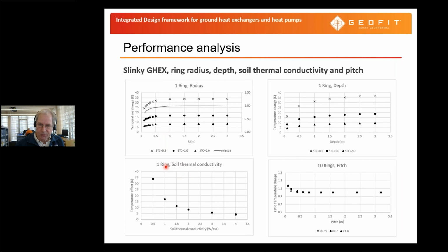We can also look at the soil thermal conductivity, and here we can see that at very low soil conductivity, like 0.5 in a completely dry sand, we have a big temperature effect of the soil thermal conductivity, but once it is above 1.5, this effect again decreases. So here we can say that if we have very dry soils, perhaps a horizontal shallow heat exchanger has a lower performance and needs a larger heat exchanger to accommodate the energy load than if you have a slightly higher thermal conductivity.